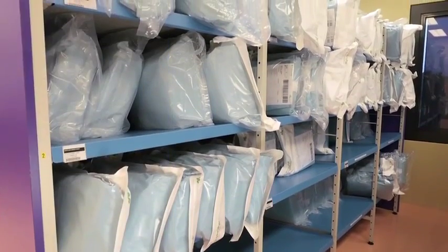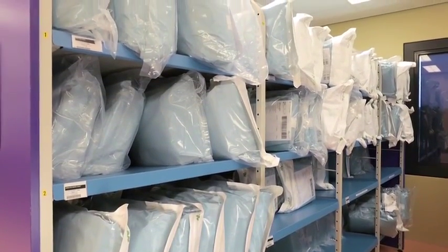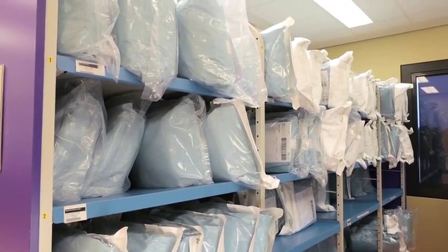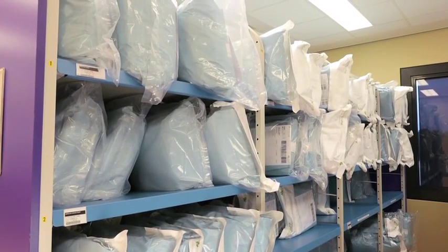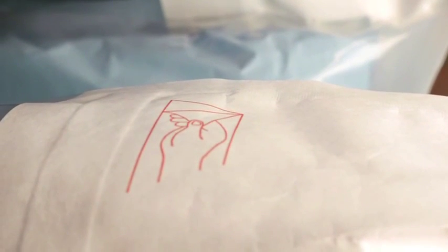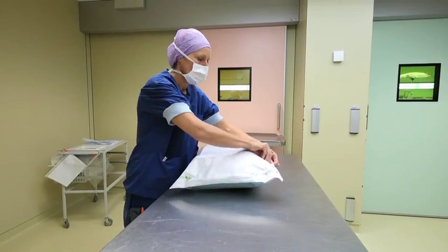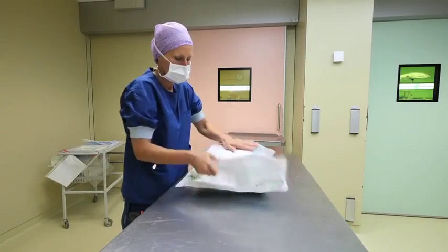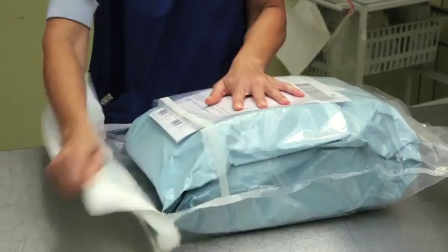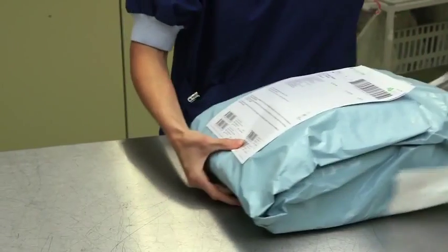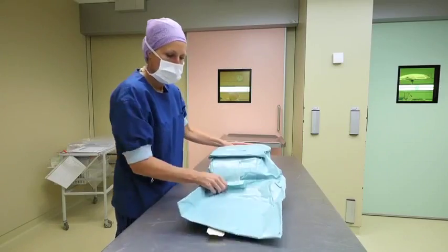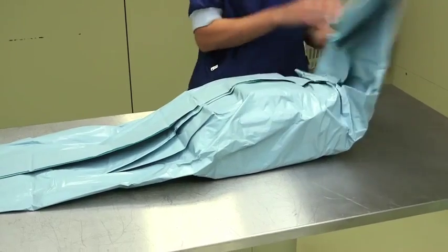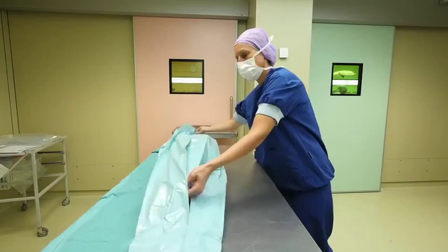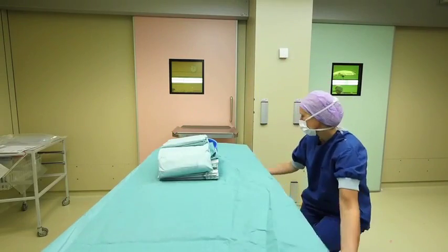Header bags are large sealed bags made usually from transparent films with one area made from a permeable microbial barrier material to allow sterilization gases to enter. Header bags are used for large items like gowns and drapes, as well as for kits or sets of devices for typical operating procedures. If several items are packed in a header bag, they are normally in a tray or wrapped in a drape, so they can be removed in one step.